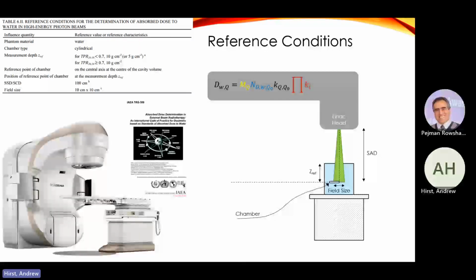So for a 6 MV photon beam, you're using 6 MeV electrons to create it. You're only going to have a few photons actually at 6 MeV. The rest are going to be some kind of continuous shape from 0 to 6. And that shape won't be exactly the same for two 6 MV beams from one linac to another. You can characterize that spectrum essentially using TPR 20/10. It's a good metric for the penetrating power of the radiation, which is related to that spectrum. So your chamber is going to respond differently, even if you're giving the same amount of joules total, the same amount of energy, but with photons of a different energy, because it has some energy dependence.